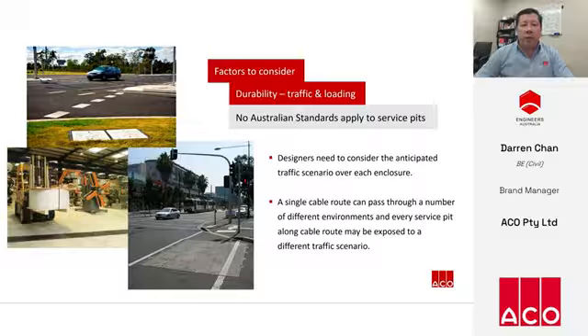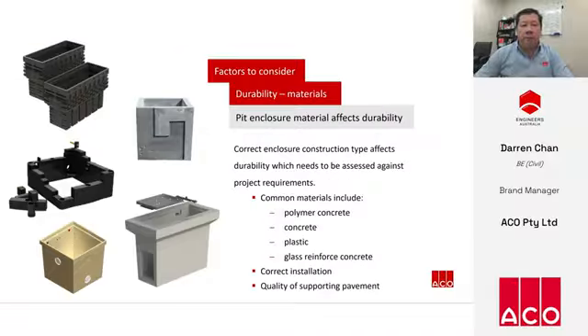There is no Australian standard that applies to service pits. Designers need to consider the anticipated traffic scenario over each enclosure, whether it be none, accidental, or deliberate, and what wheel types and loads during construction and during service. Remember, a single cable route can pass through several different environments, and every service pit along the cable route may be exposed to a different traffic scenario. A lack of consideration can lead to over-design or failure.